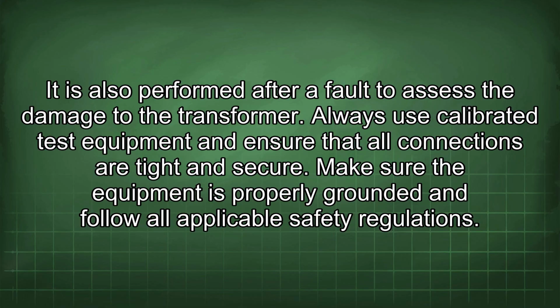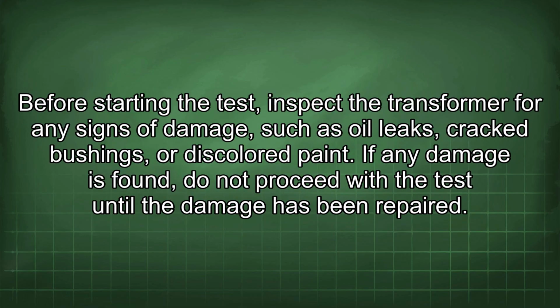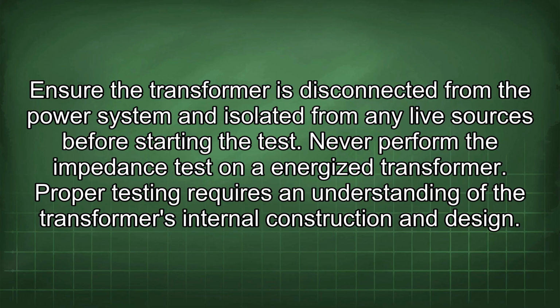Always use calibrated test equipment and ensure that all connections are tight and secure. Make sure the equipment is properly grounded and follow all applicable safety regulations. Before starting the test, inspect the transformer for any signs of damage, such as oil leaks, cracked bushings, or discolored paint. If any damage is found, do not proceed with the test until the damage has been repaired. Ensure the transformer is disconnected from the power system and isolated from any live sources before starting the test. Never perform the impedance test on an energized transformer.